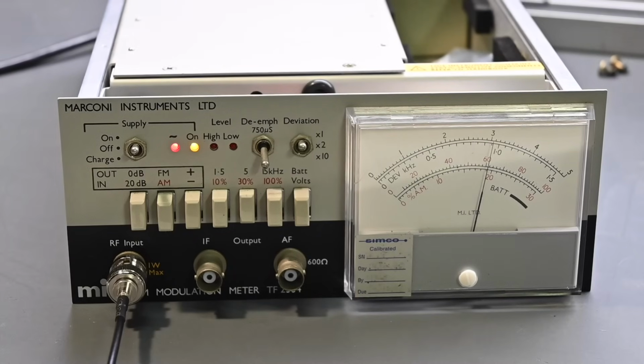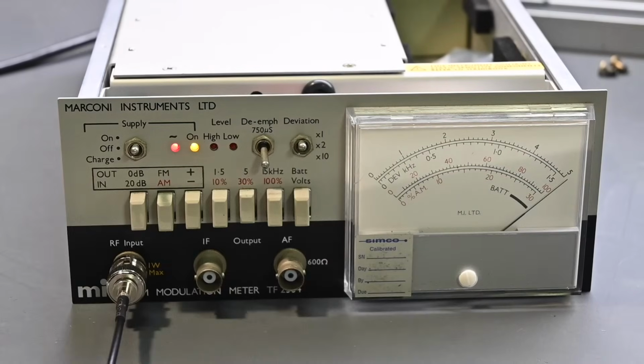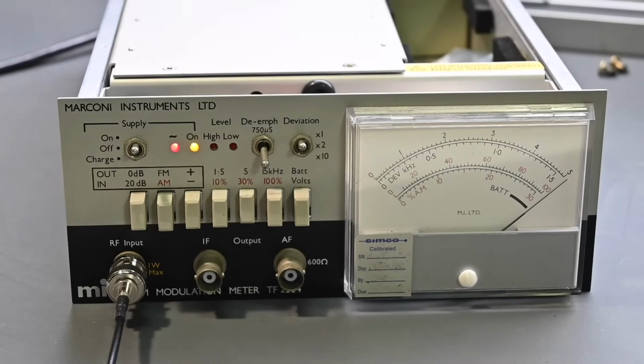If I go to 3 kilohertz, perfect. If I go to 4 kilohertz, again, extremely close. Maybe just ever so slightly above the 4 tick mark. And if I go to 5 kilohertz, now it's just a little bit beyond the full scale, right at 5. So what's happening is we're reading a little bit high on the high side, a little bit low on the low side. It's a little bit of a linearity issue on the meter. But again, the readings are extremely close, so I'm not seeing really any major problems there. And perhaps it could be touched up with some other calibrations, but that's for another time. This looks very, very good at this point.